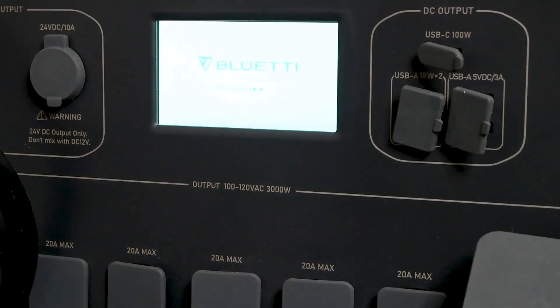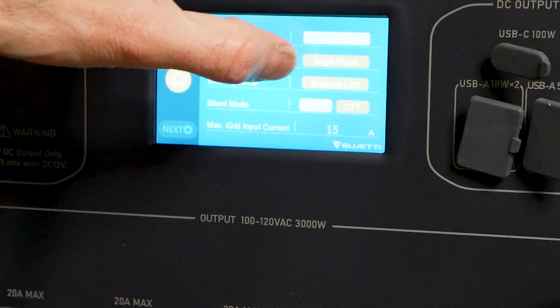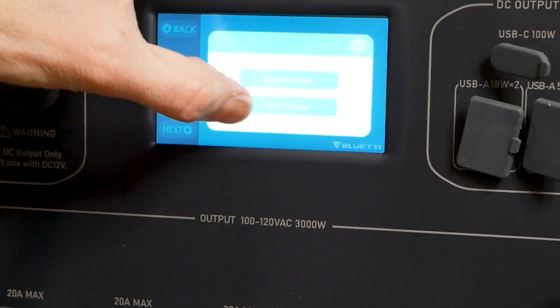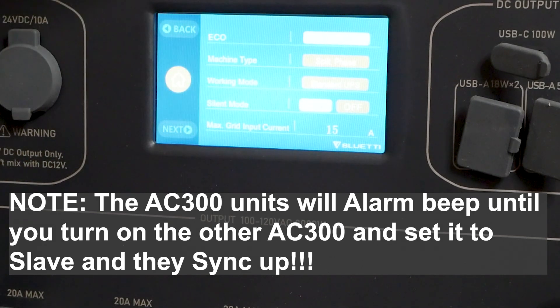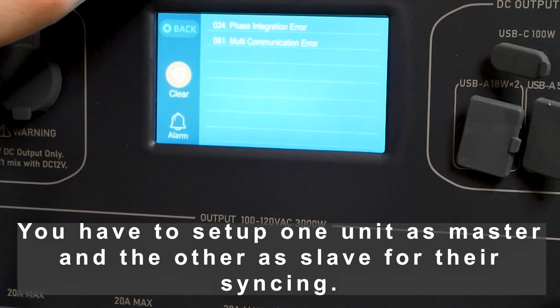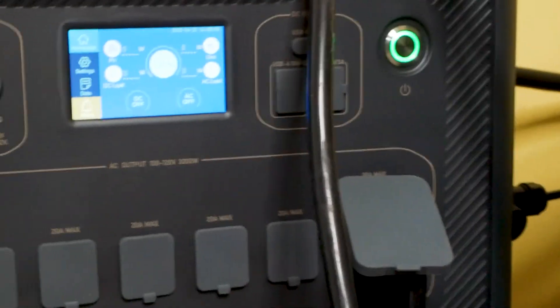The whole reason why I bought these is because I need to go split phase. This one's off over here and this one's on. Going into Settings — next screen — machine type: split phase. We'll put this one as master. It's giving me an error though. Multi-phase integration error — communication error. I'm going to see if it'll talk to the other one.